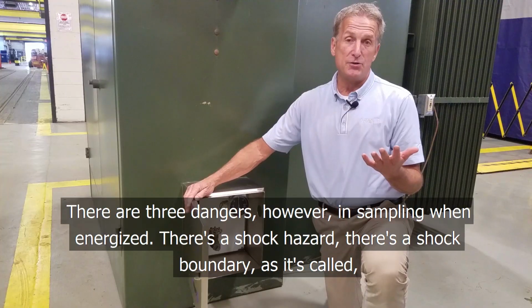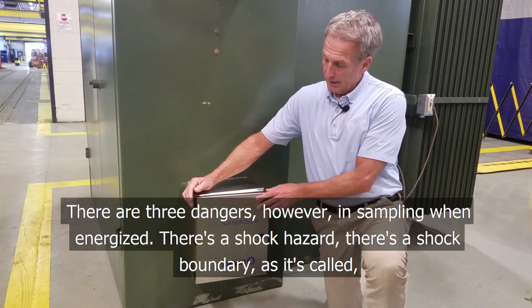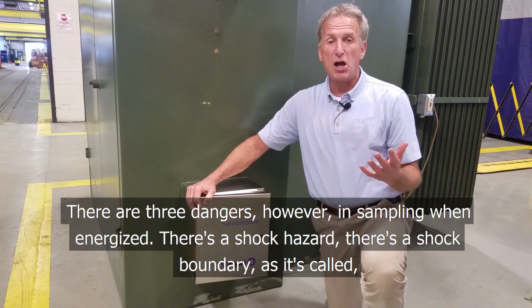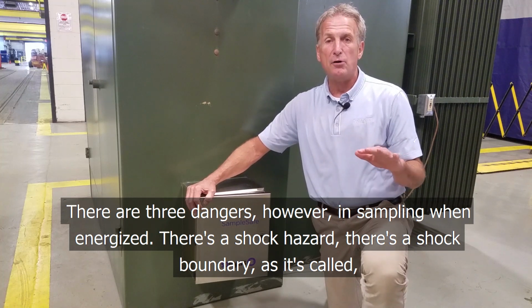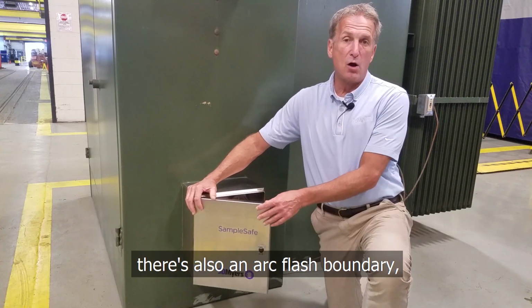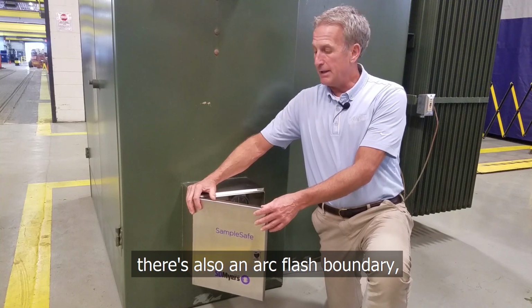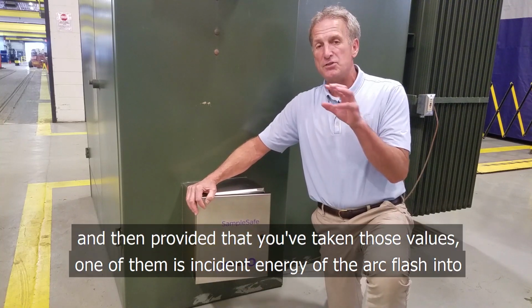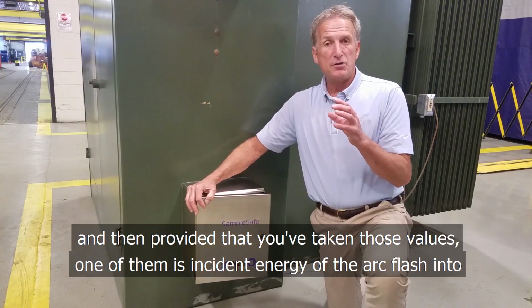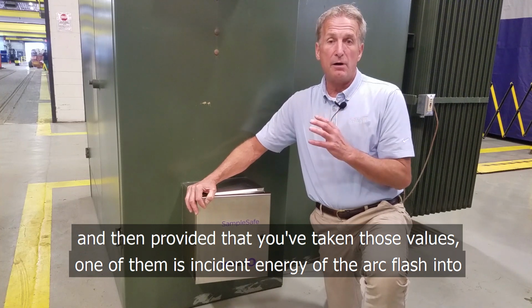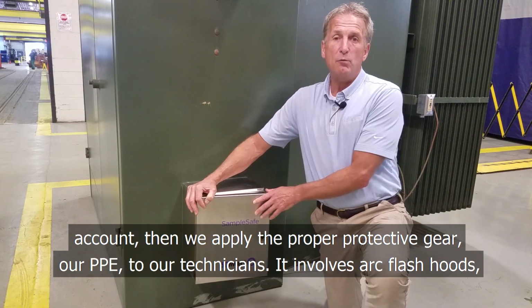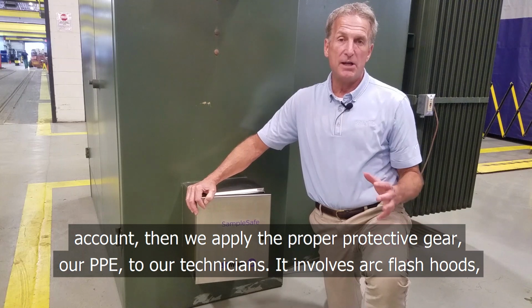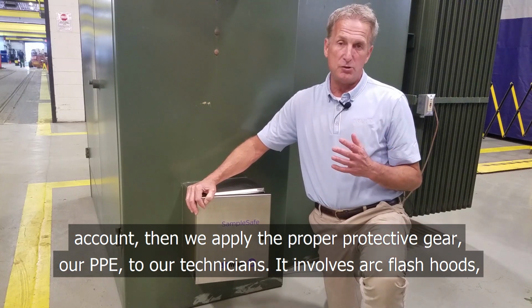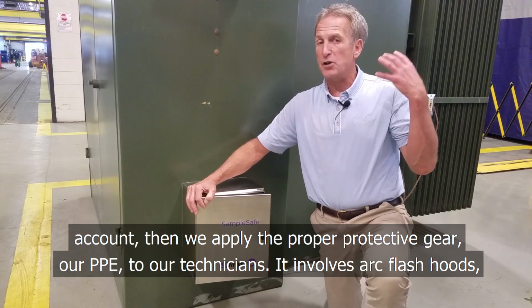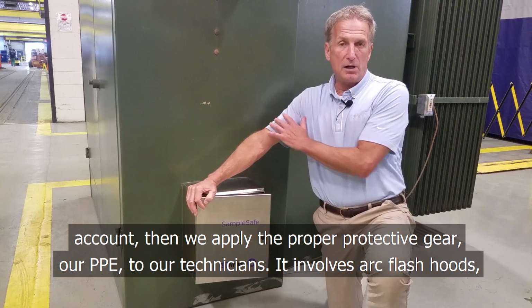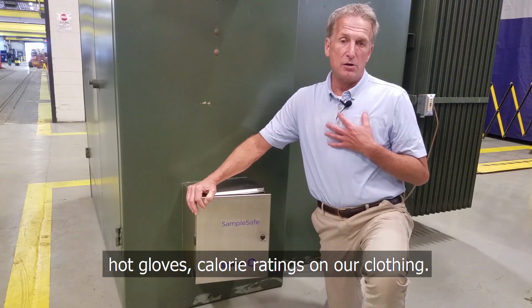There are 3 dangers, however, in sampling energized. There's a shock hazard, there's a shock boundary as it's called, there's also an arc flash boundary, and then provided that you've taken those values, one of them is incident energy of the arc flash, into account, then we apply proper protective gear, our PPE, to our technicians. It involves an arc flash hood, hot gloves, calorie ratings on our clothing.